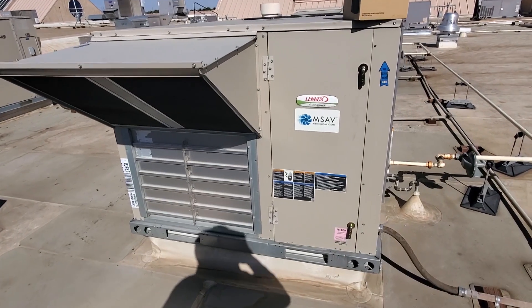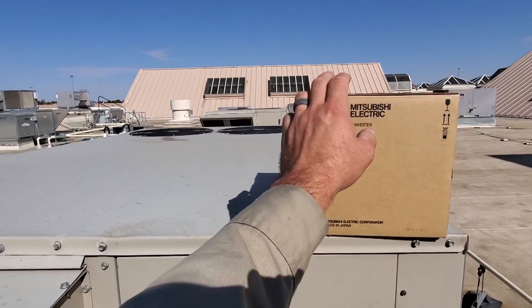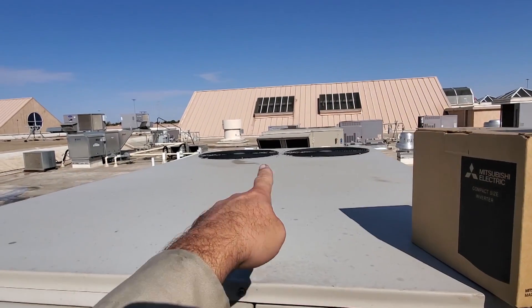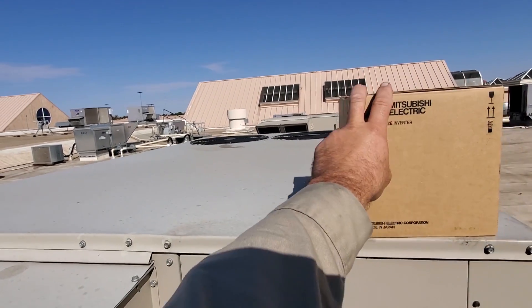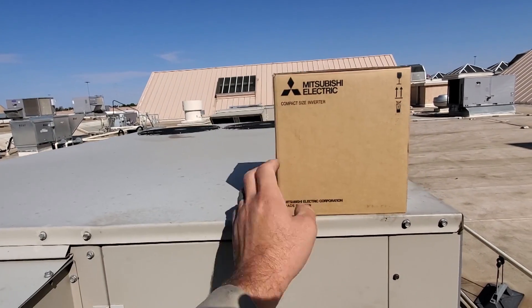We've got a Lennox Energence unit that we need to put a new VFD on. I've talked about this before because I've done a repair on this where I had two bad capacitors for the conventional fan motors. Took a while to get the VFD, but we're going to go ahead and replace it now.